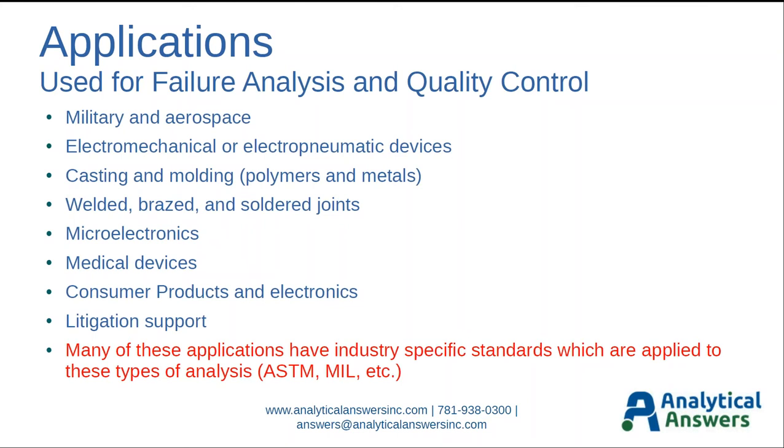Many of these applications have industry-specific standards which are applied to these analyses. For instance, ASTM, MIL, and many others. For instance, medical devices for surgical use are measured by ASTM F640. You're trying to measure how opaque those devices are when they would be placed in the human body to make sure that a surgeon using them with a fluoroscope would be able to see them when they're using them so they can properly place devices inside the human body.